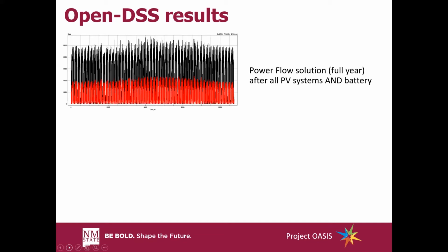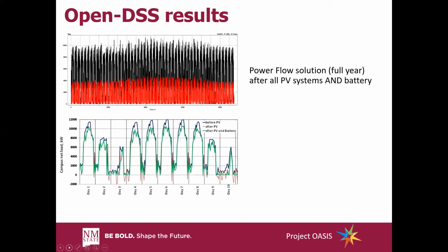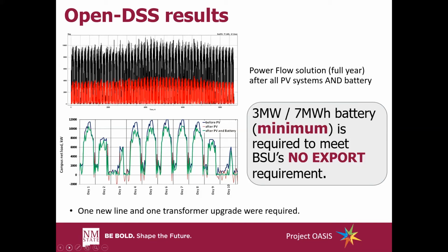As you can see, all negative power export has been remedied. The figure on the bottom left shows the same information, net campus load before PV with all PV systems added and after battery system addition, but is expanded to see better details. These results show that in order to achieve zero power export, BSU's use case required a minimum of 3 megawatt, 7 megawatt hour storage.